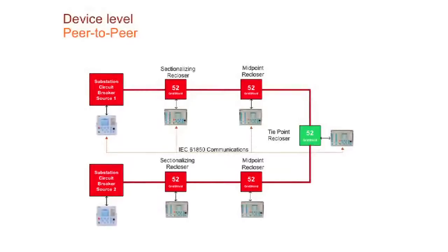Some of the applications right now are what we call substation based. So you have a gateway at the substation. In this case, we have a COM600, and through your communication network, the only key part is that all these IEDs are on the network. Right now I have GridShield reclosers with RER620, but if you have a switch in the tie point, as long as it supports open protocols like DNP, 61850 or Modbus, then you can talk back to a communication gateway. That communication gateway gets all the data, and on top of the communication, it also has a PLC that has the logic that performs the isolation, not only the fault detection. The fault detection is done automatically by the recloser based on curves and protection settings. But then the isolation and the restoration is done by a device at the substation. So in the same case, you have a fault here. This one goes to lockout and sends through the network a lockout message to this device.